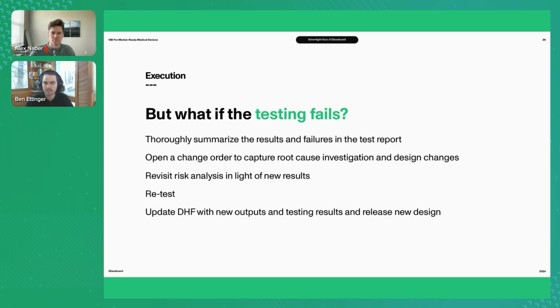In your test report, thoroughly summarize the results. It's common to see folks get a failing result and just want to toss it out and keep redoing until they get a pass, but that cuts out so much of the story. Describe the failures, describe what you're going to do about them, open a change order to capture the root cause investigation and resulting design changes. Always revisit your risk analysis in light of the new results, conduct retesting as needed, and repeat that iterative process until you get the results you need, then update your design history file with the new outputs and testing results and release the new design.